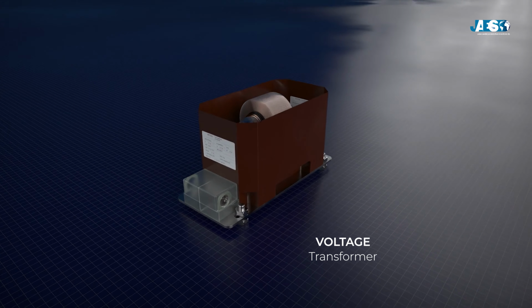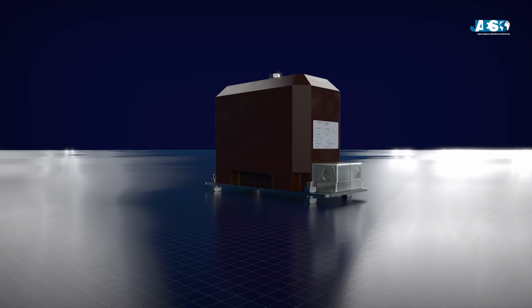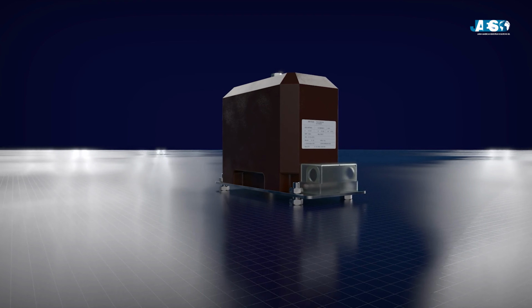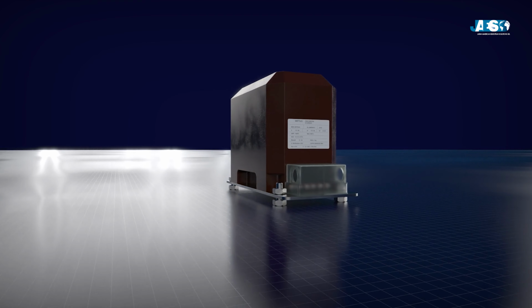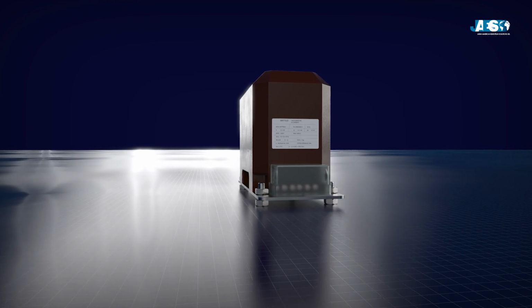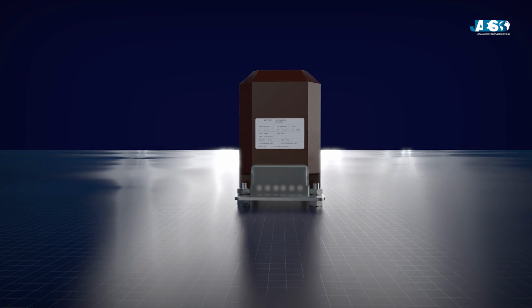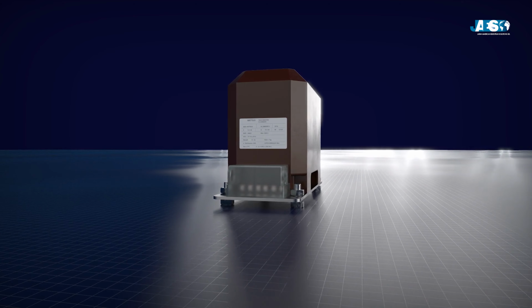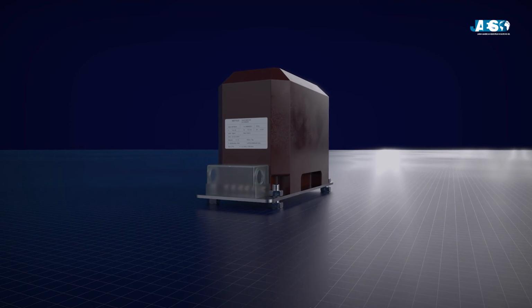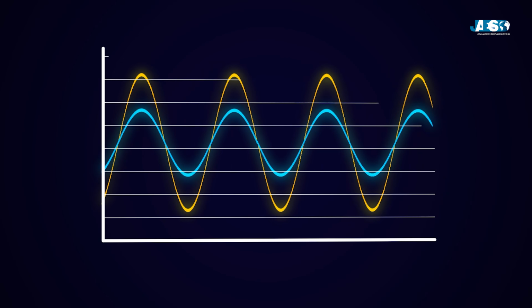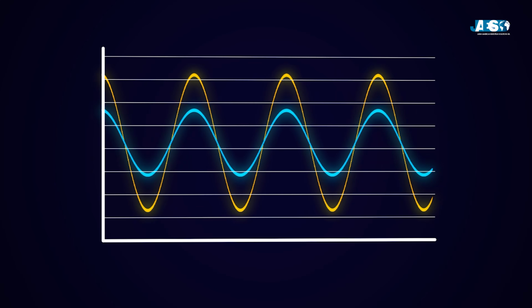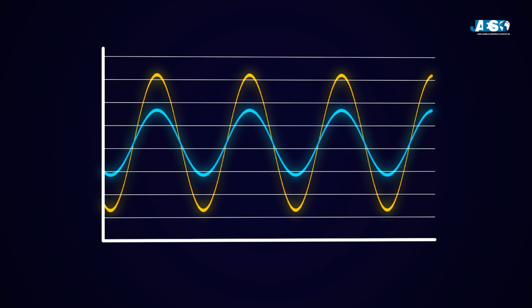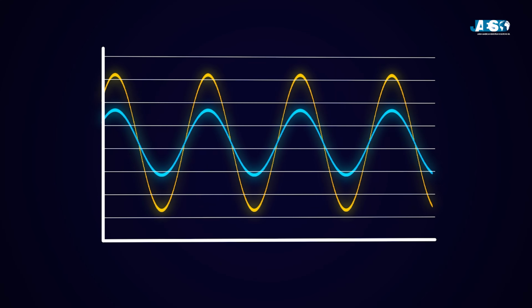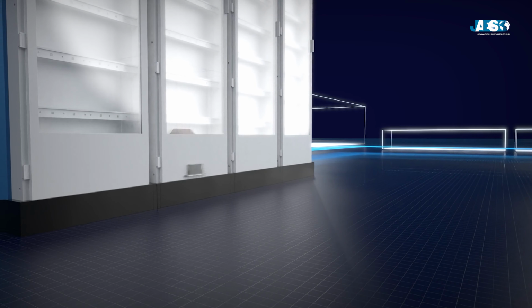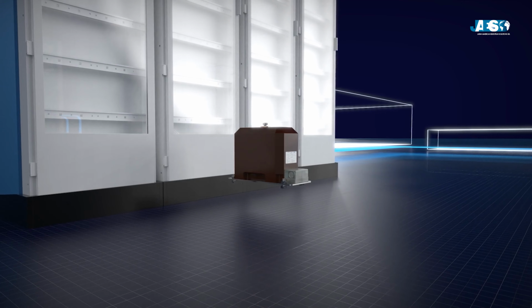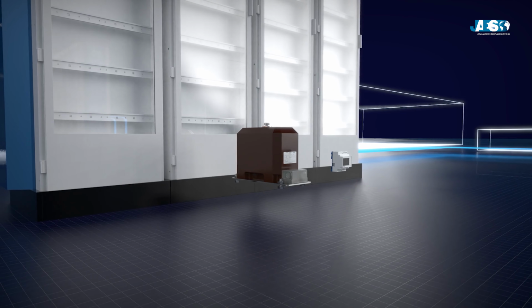Now, let's take a look at voltmetric transformers. A voltage reducer, or VT, is a transformer capable of supplying its output terminals with a voltage of a value congruent with the available measuring instruments, and such that it faithfully represents the input voltage. The voltage at the secondary is reduced in amplitude by a known amount with fixed accuracy and is in phase with the primary voltage with fixed accuracy. The voltage reducer is connected in shunt to a line whose voltage needs to be measured and has a voltmeter at the secondary.